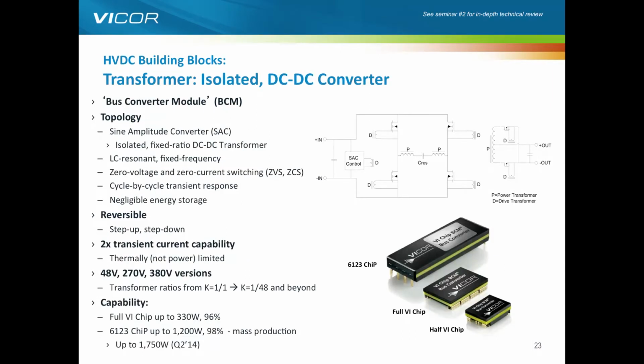The other element we've got here is our DC to DC transformer. So this is our voltage step down or step up with isolation unit. In this case, we're saying it is our sine amplitude converter topology. And the reason it's a sine amplitude converter is because we put in DC, we switch the MOSFETs on the primary side to create a sine wave that crosses the transformer gap. And on the secondary side, we do full wave rectification back to DC. It's called sine amplitude because the amplitude of that wave changes with load. So as the load increases in step function, the amplitude also changes. So that's the reason for the name.